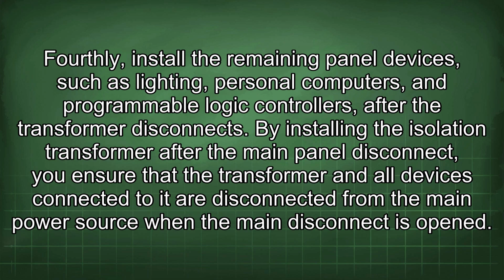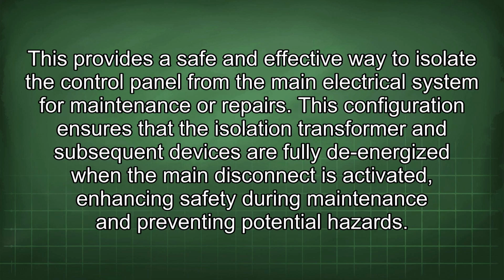By installing the isolation transformer after the main panel disconnect, you ensure that the transformer and all devices connected to it are disconnected from the main power source when the main disconnect is opened. This provides a safe and effective way to isolate the control panel from the main electrical system for maintenance or repairs. This configuration ensures that the isolation transformer and subsequent devices are fully de-energized when the main disconnect is activated, enhancing safety during maintenance and preventing potential hazards.